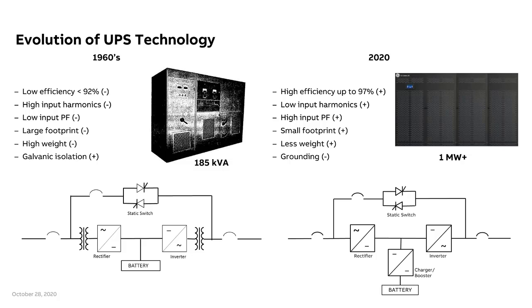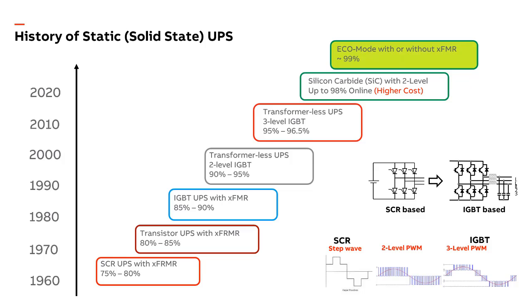The main difference is that back then we needed very heavy filters and transformers, a lot of magnetics to make this work, to protect the semiconductors against too high voltages and to filter out a lot of harmonics. Modern UPSs are based on transistors, actually IGBTs, very fast switching. I'll go to the next slide. At the bottom right, it just shows how better and better components, from SCRs to bipolar transistors to IGBTs, can now be switched so that the switching pattern is very close to a sine wave. This is true not only on the inverter side, but on the rectifier also. So we don't need the big transformers and the filters anymore. And the driver for this is, like we see, steps almost at a step a decade, with the improvements primarily in efficiency, but certainly this has made UPSs a lot lighter and a lot more compact and improved the efficiency dramatically as we've gotten rid of all the heavy magnetics.